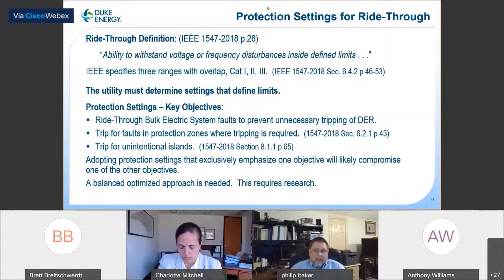It boils down to avoiding unnecessary tripping, but yet tripping when required. That turns out to be a fairly difficult thing to achieve. Adopting protection settings that exclusively emphasize one objective may compromise one of the other objectives. So a balanced approach is needed, and research is needed to optimize these settings for the best performance.